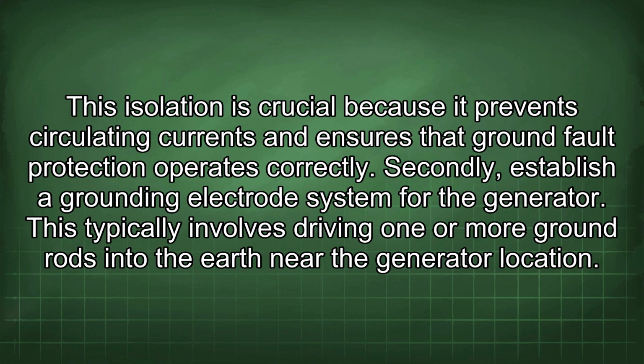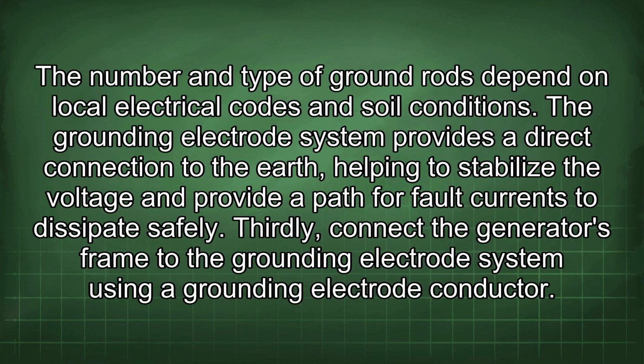Secondly, establish a grounding electrode system for the generator. This typically involves driving one or more ground rods into the earth near the generator location. The number and type of ground rods depend on local electrical codes and soil conditions. The grounding electrode system provides a direct connection to the earth, helping to stabilize the voltage and provide a path for fault currents to dissipate safely.